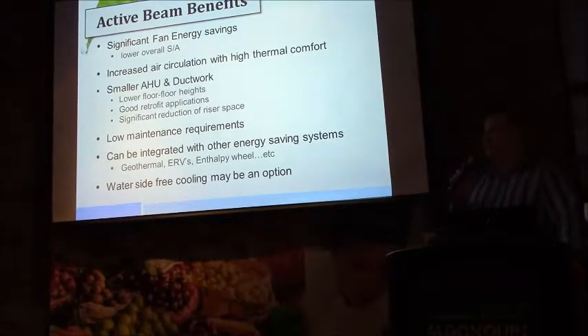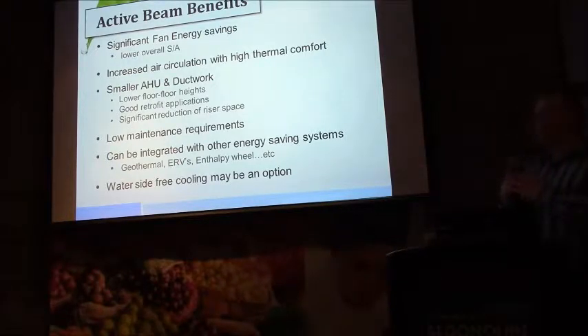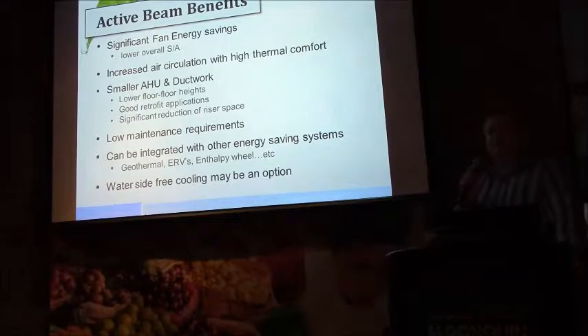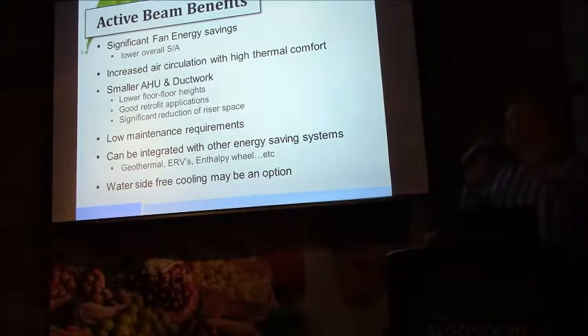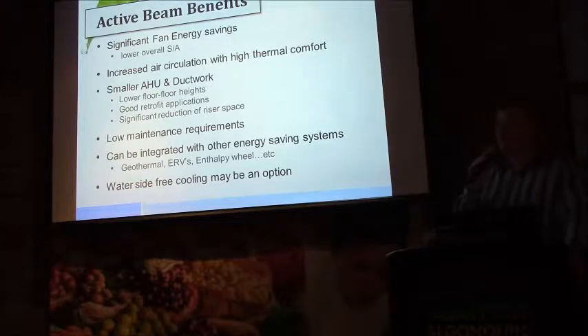The other benefit as well is the individual zoning capability. So for the cost of a two-position control valve and a thermostat, we can achieve some LEED credits relative to individual room temperature control. Again, a large benefit. They've been coupled to geothermal heat pumps, where they've been used as a water-to-water heat pump, and on their piping array used for load shifting. So they'll be cooling in the core and heating the perimeter in the off-peak season. And through the mechanical room, those water streams can be effectively managed to shift the loads from the heat of rejection on the water loop to the perimeter where it's needed.